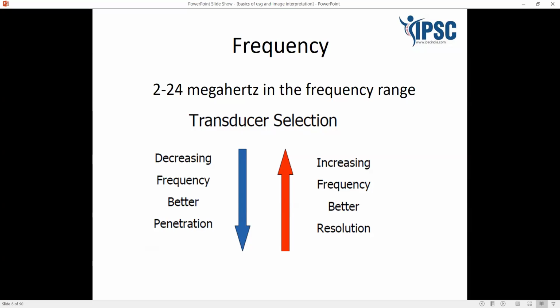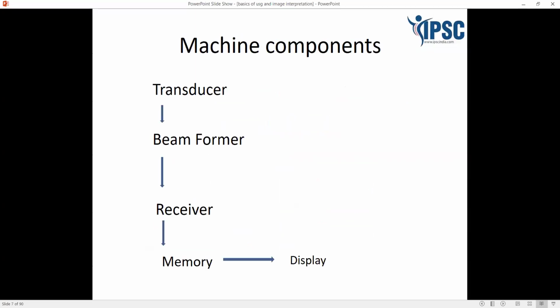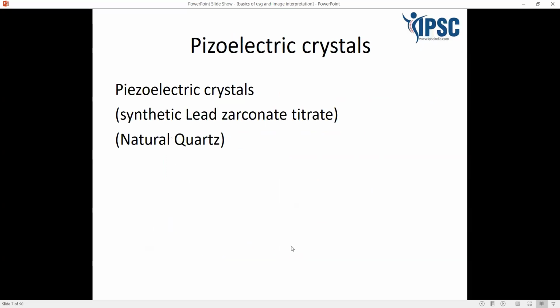For example, if you're wanting to scan a hip, the hip joint is a deeply placed structure. So we need a low frequency probe. But if you're wanting to scan something superficial like the rotator cuff of the shoulder, then we need a high frequency probe. So now the ultrasound machine has got various parts. We've got a transducer, a beamformer, a receiver, a memory and a display. These are the various structures which are there in the machine.